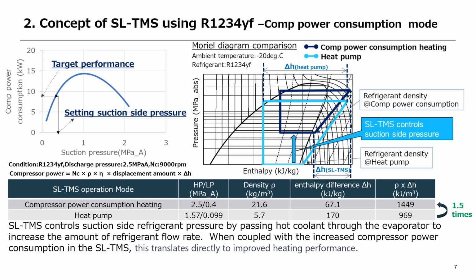In the heat pump mode, as indicated in the table, the system absorbs heat from the ambient environment. This causes the low-side refrigerant pressure to drop into negative territory, resulting in reduced refrigerant density. Consequently, despite a significant enthalpy difference, the heating performance remains suboptimal. In contrast, the compressor power consumption mode exhibits a smaller enthalpy difference, originating from the difference between the compressor's discharge and suction sides. However, by elevating the low-side pressure to the desired level, we can boost the compressor suction density, increase the refrigerant flow rate, and thereby achieve effective heating performance.